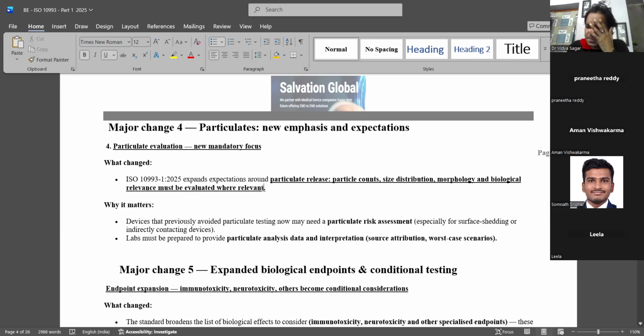See, this is a very, very tough job to do, a particle count on any devices, basically for those which come in contact with the human body and more importantly with the blood. Okay, because if you look at the 10993 flowchart, there will be three things. One is contact time, the duration of contact, as we discussed, there will be three categories. The other category where we need to link up that matrix of table is in which area it is going to get in contact. It's going to be on the surface, or not contacting at all, or just on the skin surface, or a breached or compromised area on the skin, or it is getting contact with the circulating blood or not with the circulating blood. Okay, or it is for intravascular surgeries where it is totally connected with the central circulating blood with the heart.